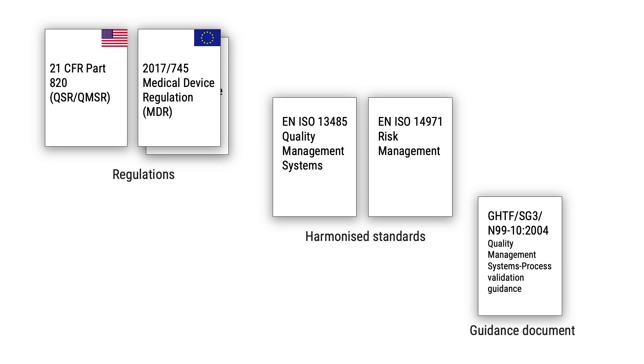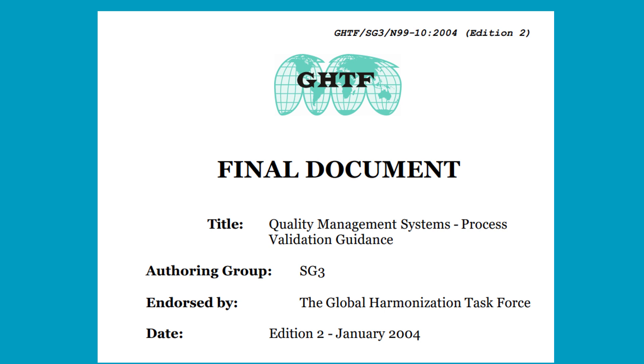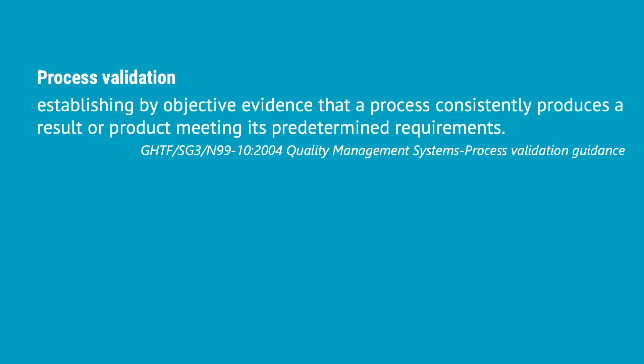GHTF stands for Global Harmonization Task Force. The GHTF was an international group consisting of regulatory authorities and industry representatives, and one of their aims was to put together guidance documents related to medical devices. In 2011, the GHTF group was replaced by the International Medical Device Regulators Forum, abbreviated IMDRF. However, the 2004 GHTF guidance document on process validation still remains applicable. The GHTF states that process validation is establishing by objective evidence that a process consistently produces a result or a product meeting its predetermined requirements — a systematic series of tests and evaluations that verify whether a process can reliably produce a product that meets its predetermined criteria under normal conditions.